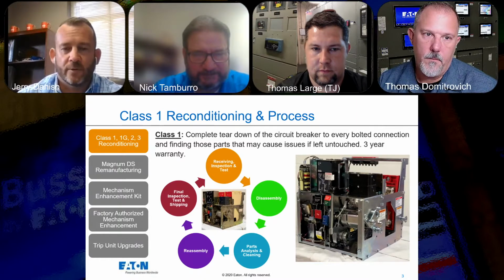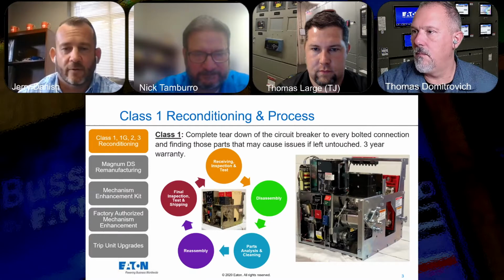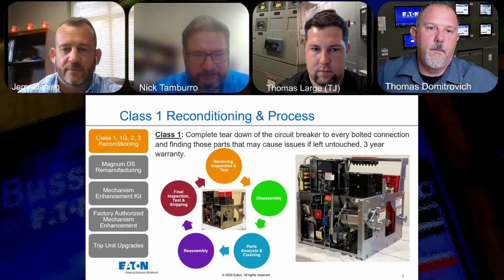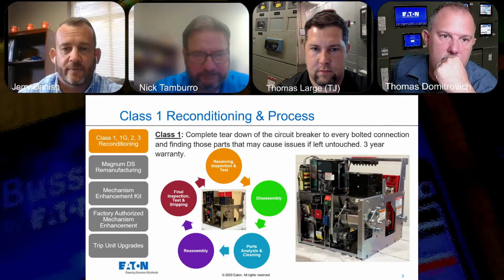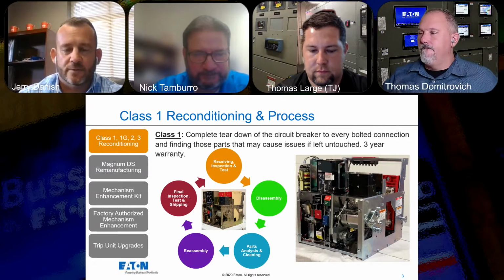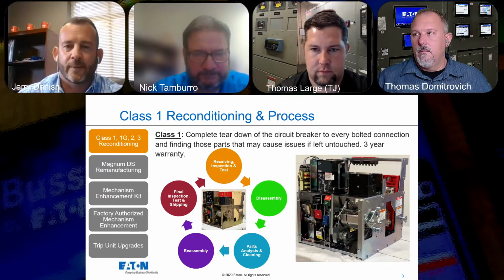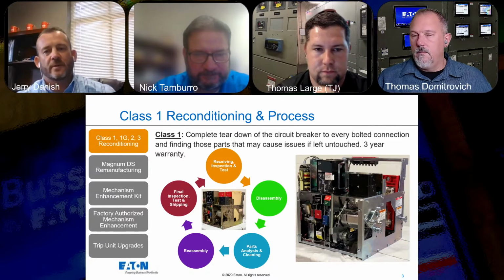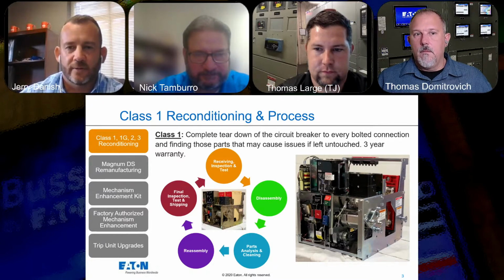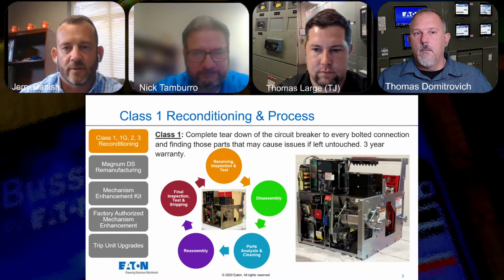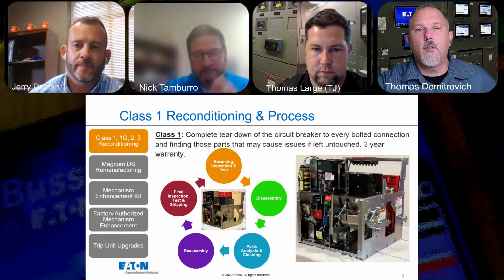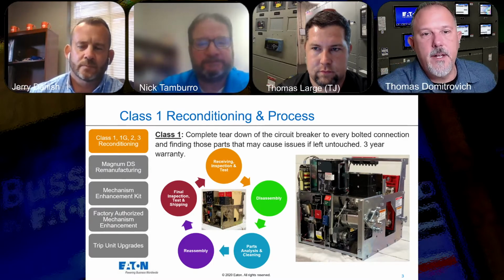Just keep the old trip unit on it, or as we all kind of talked about, we can enhance that trip unit to give you better selectivity for coordination, new safety features, and also, depending on what trip unit you go with, communications. So if you need better insights into your electrical system, or you have a control room, or any power monitoring system, all this can be wired into that to give you, like I said, better insight into your power system and what's going on. What about interrupting rating? Can I change the interrupting rating of that breaker?